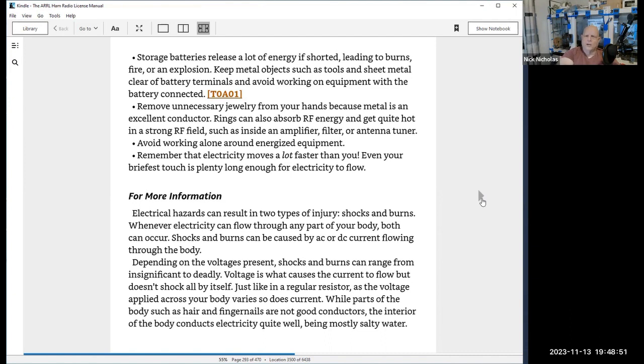Always avoid working around energized equipment. Turn it off, ground it with safe grounding practices, and study up to do that. Google it, whatever. Don't try something you've never done before on your own. Get somebody to show you if you don't know. And remember, you're not fast enough to touch something and let go like feeling the side of a hot pot. If you touch something electrical that's high enough current, especially DC, you can't let go, you can't move away from it. You're going to get in serious trouble.